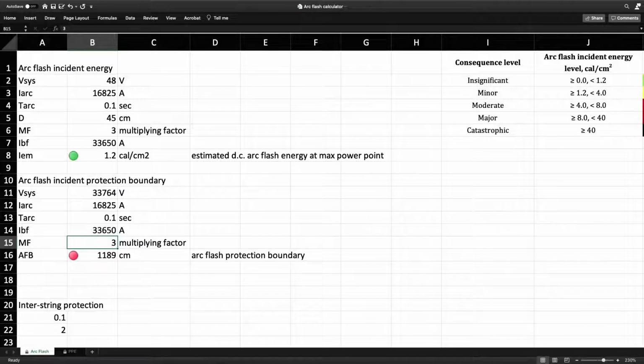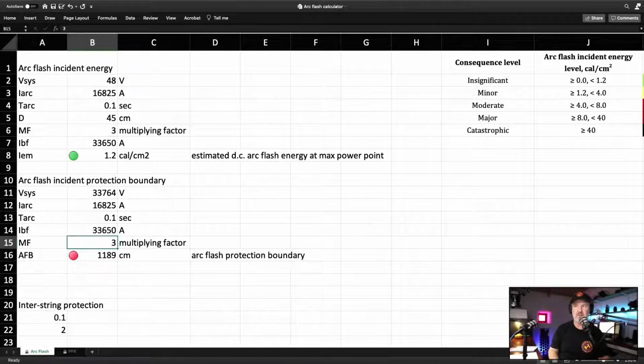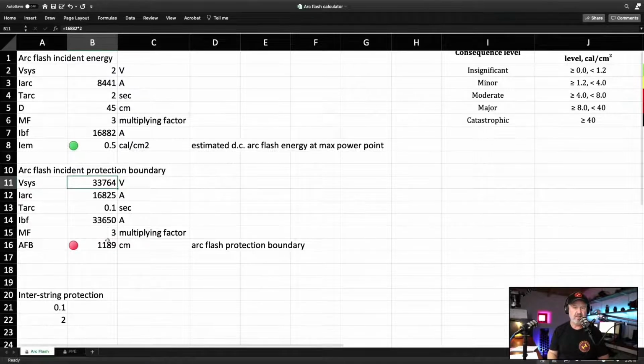So I'm going to go back to my little spreadsheet. So here I'm on the spreadsheet. I'm going to just work it out. So here at a cell level, it's 2 volts, not 48. I don't have any intercell overcurrent protection, and my bolted fault current is 16,882 amps. And it's not so bad. And it's inside a box, so it's a multiplying factor of 3. And by the way, if you wondered what D is, that's working distance. It's deemed to be arm's length, so that's where that came from. So that's not so bad at all.